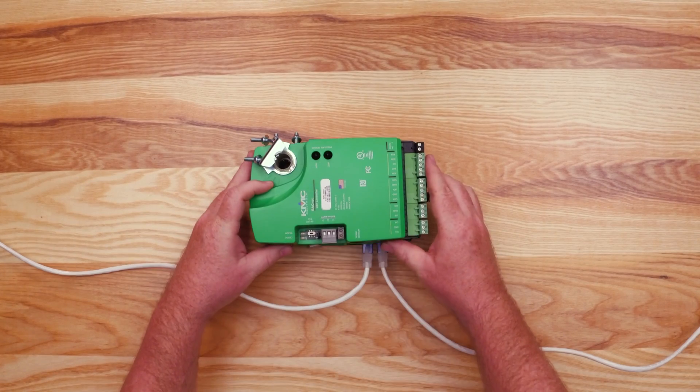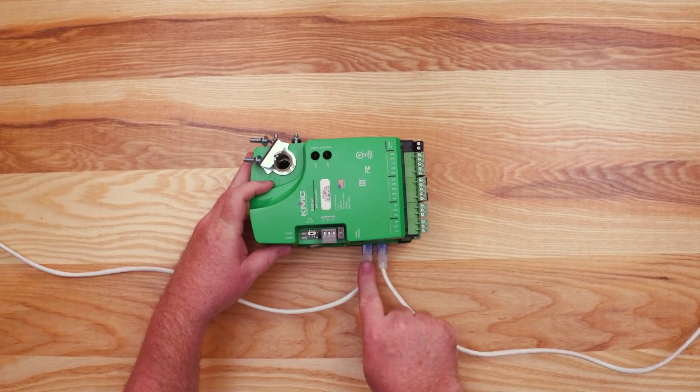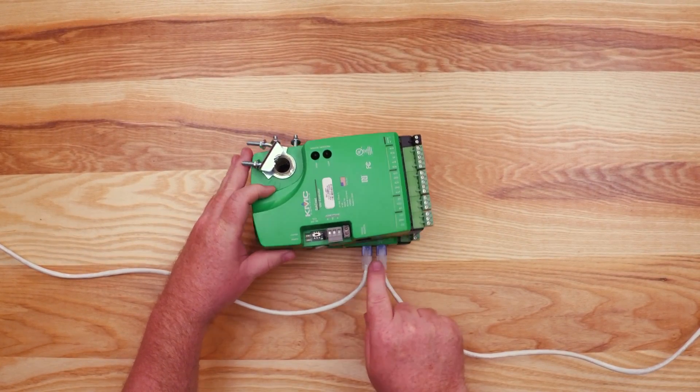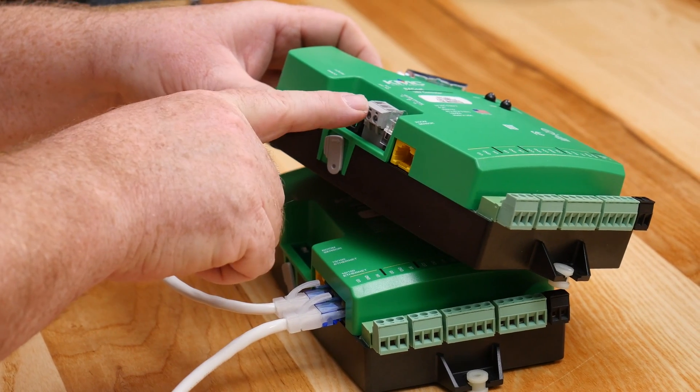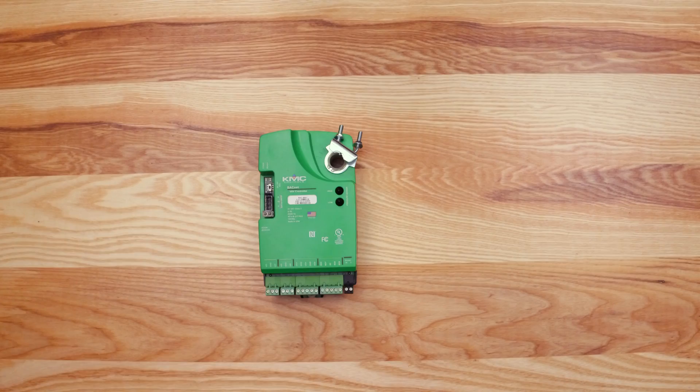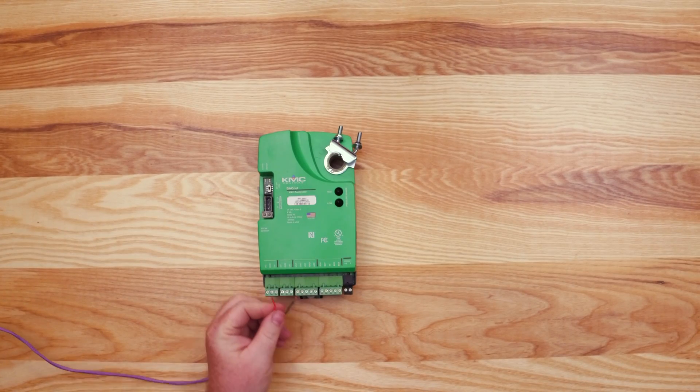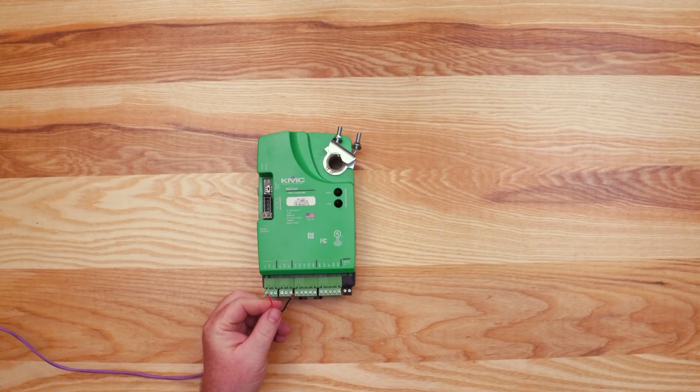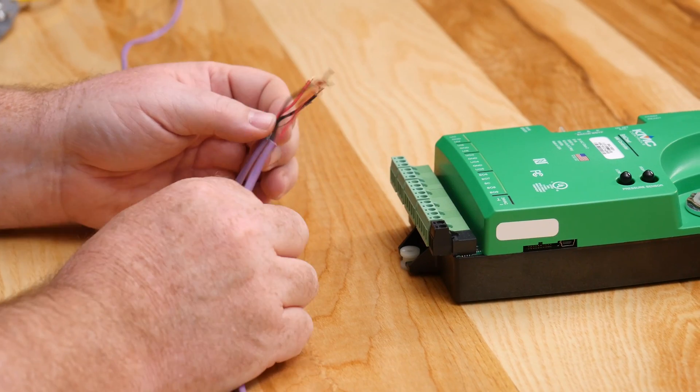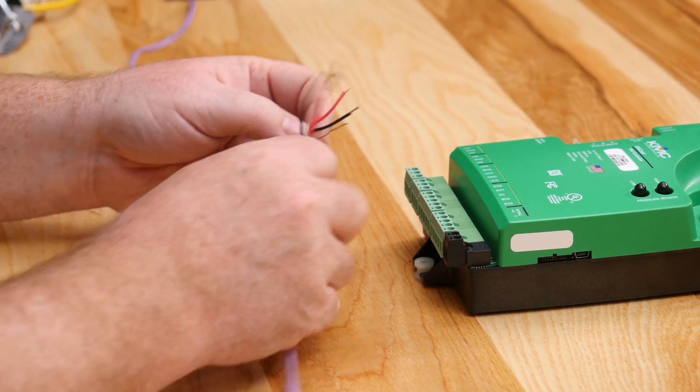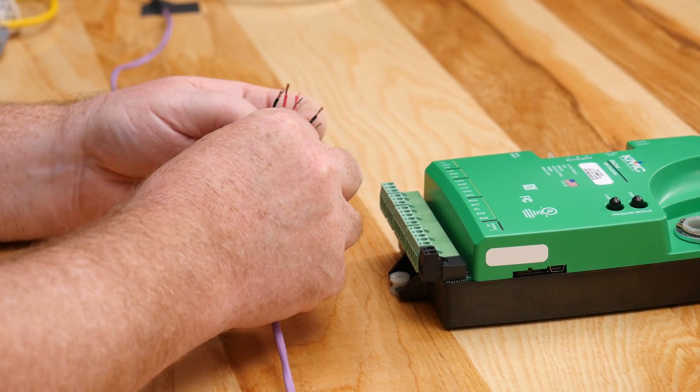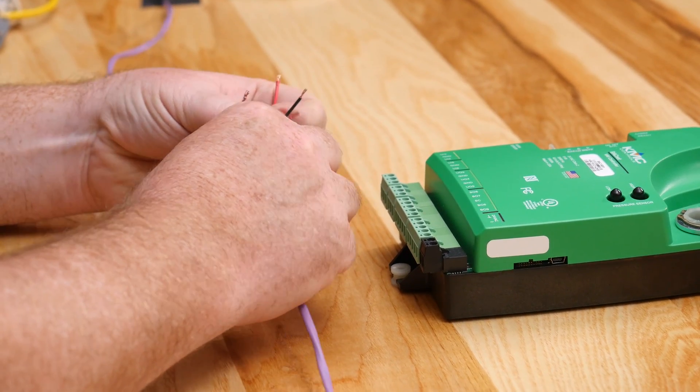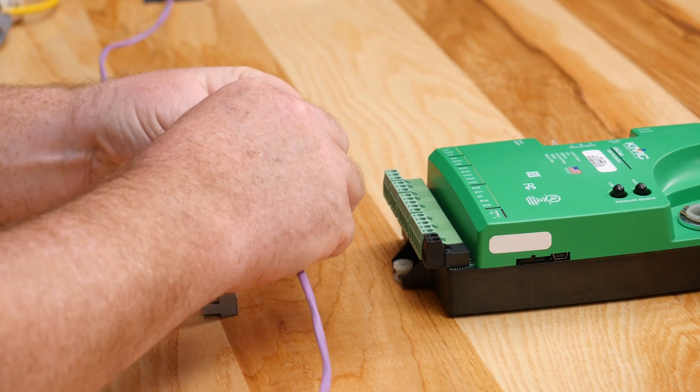We also offer a BACnet over MSTP version, where the two Ethernet ports are replaced with an MSTP terminal block. When wiring to a BACnet over MSTP network, you will have three wires. Make sure to use 18 gauge shielded cable for your network.